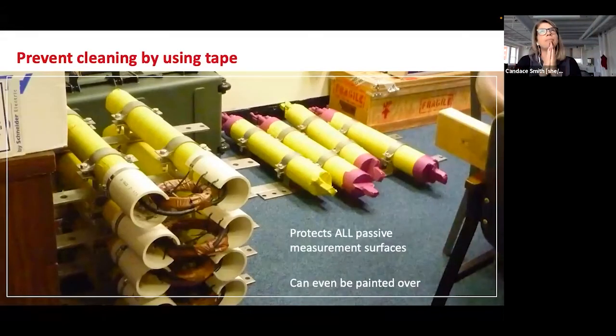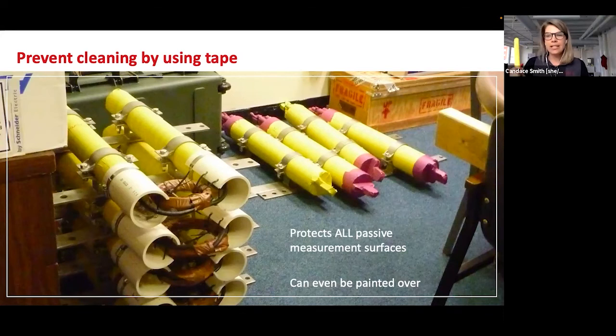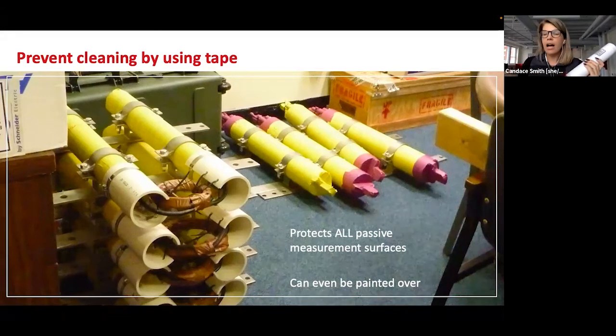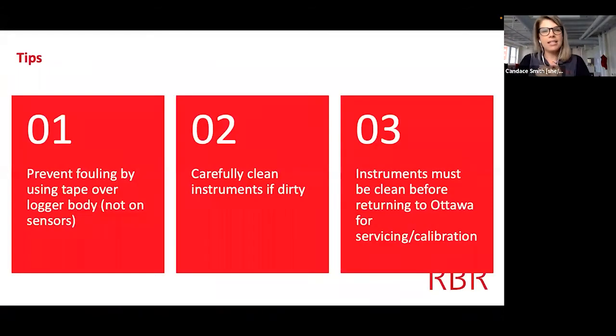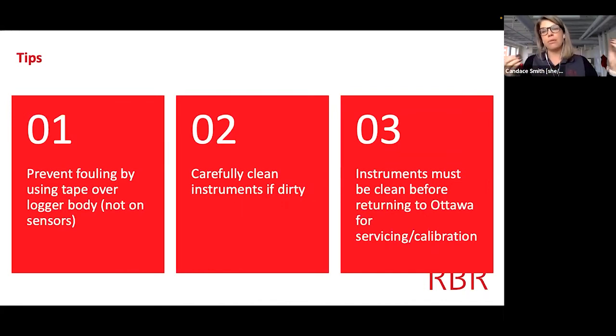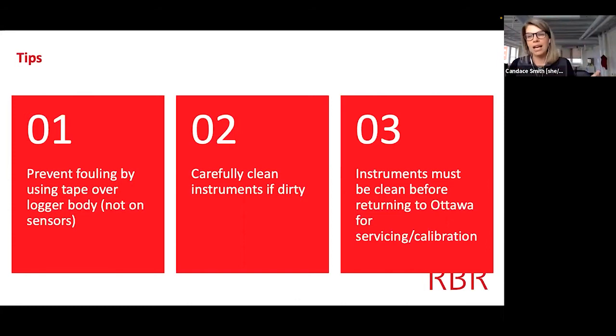For cleaning, my top tip is to prevent the cleaning by using tape. You can wrap the loggers in painters tape or masking tape, and when they come out of the water — typically after being moored — you can just cut the tape off and the logger is as good as new underneath. You can also paint the tape, not the instrument. If you're not using tape, be careful cleaning so you don't damage the sensor or gouge anything. And the instruments must be cleaned before returning to Ottawa for servicing and calibration — we'll charge a cleaning fee for dirty instruments.